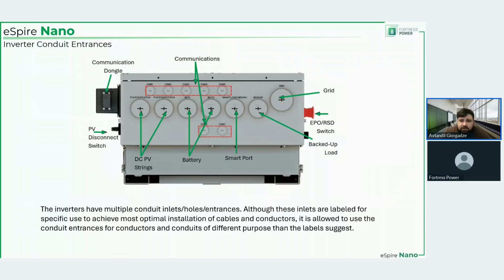Next, now it's getting a little more interesting, at least for me. The inverter has multiple conduit entrances. So far, there are no conduit entrances on the backside of the inverter. You have some on the sides, and you have some on the bottom, and they are labeled. If for whatever reason you find it easier to connect the conduits against the label designation, you're welcome and free to do it. That's totally fine, as long as the cables get to the right place. Not using the conduit entrances as labeled is totally fine.